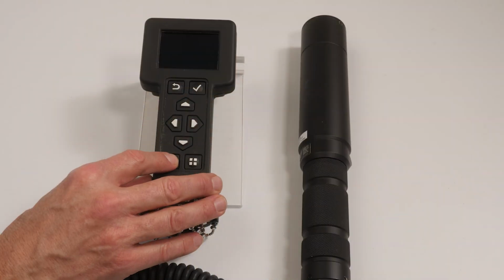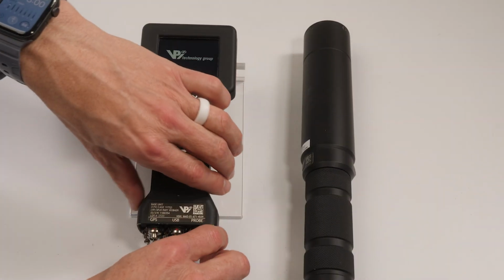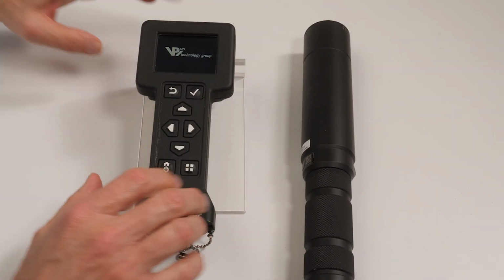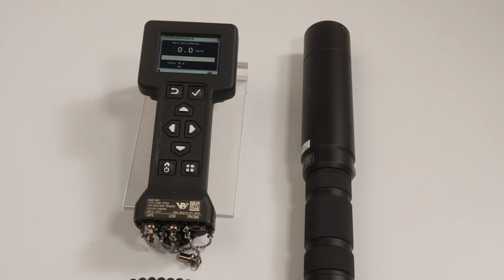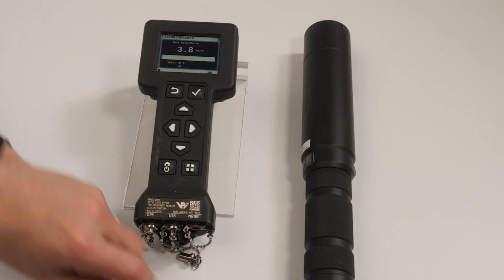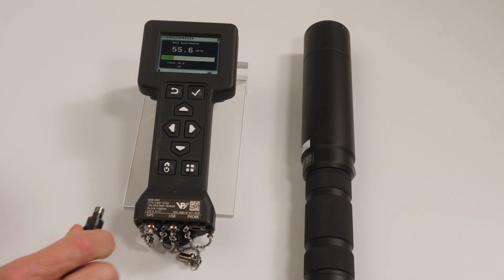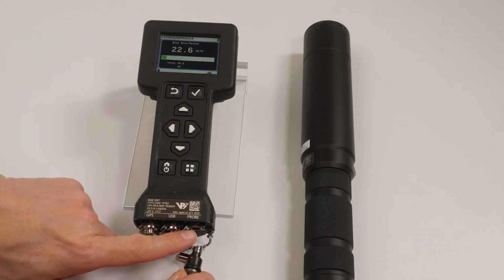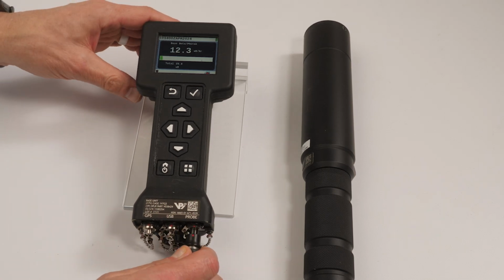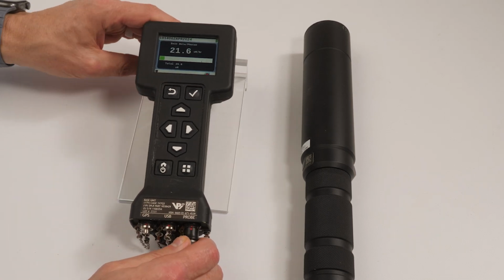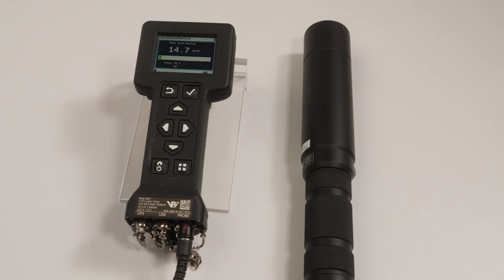To operate the sensitive gamma probe, first power on the base unit. Remove the probe connector protective cap from the base unit. Connect the common probe cable by aligning the red dot on the base unit's probe connector to the red dot on the end of the common probe cable collar. Insert until the connection is secure.